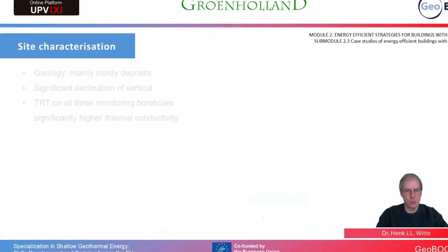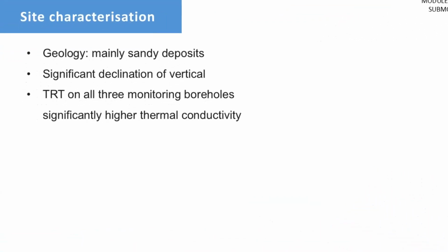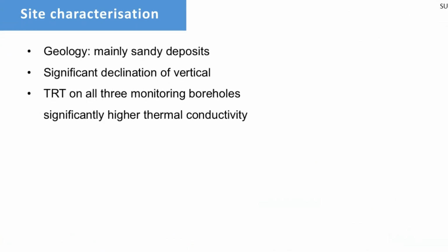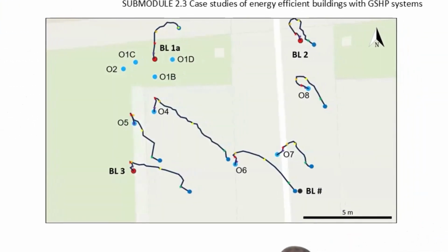Here we see some results of the geology and the thermal response testing and the declination measurements. The geology is mainly sandy deposits, so we would assume a fairly homogeneous soil profile. If we look at the picture of the deviation of the vertical on the right, we can see that there are really significant deviations with depth, which is important because in the protocol we also say things about the minimum spacing between boreholes to prevent one borehole from hitting another one. And actually these declination measurements supported the rules that we have in the protocol at the moment for minimum spacing between boreholes as a function of borehole depth.